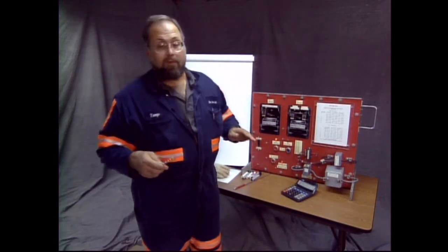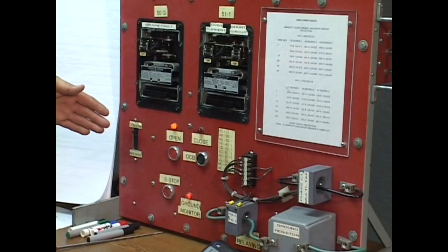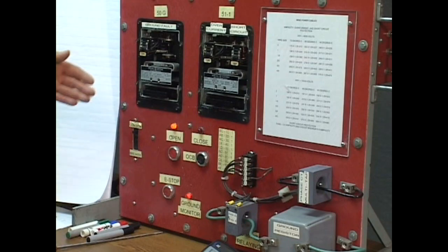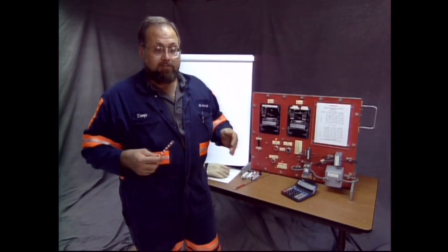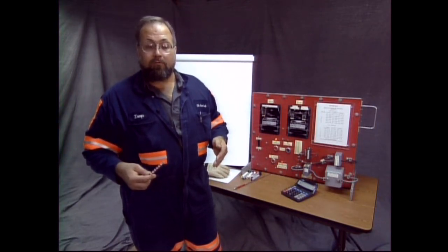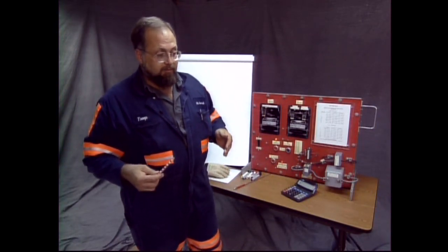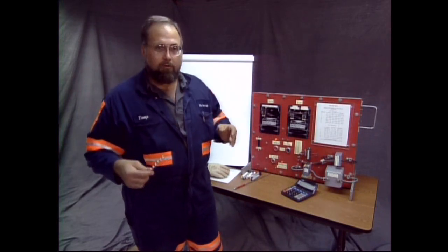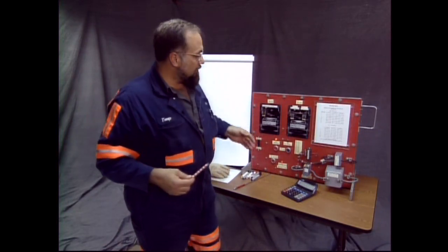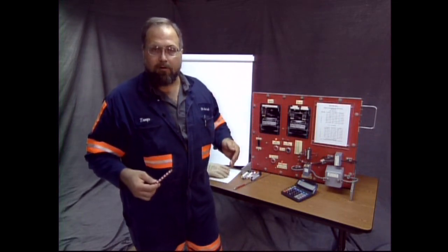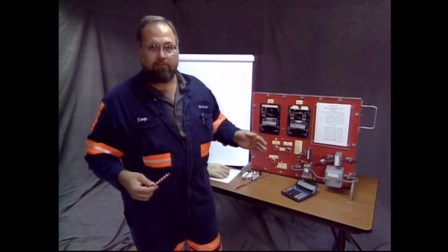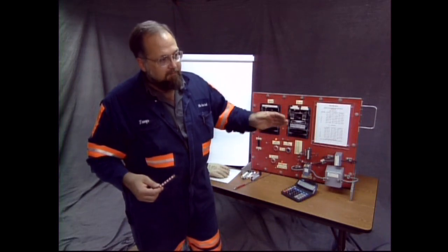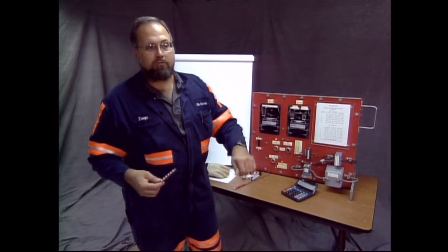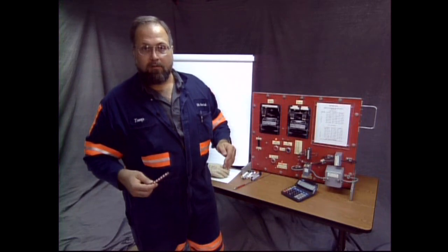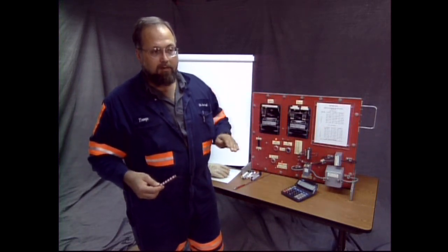So it has to be a visible, power removed. You're going to break the circuit with the oil circuit breaker or the vacuum breaker. It is designed to extinguish an arc if there is an arc. You know, you have all of your capabilities of breaking the circuit in the vacuum breaker. After you take the power off with the vacuum breaker or the oil circuit breaker, then open a visible. Look at the visible. Don't just operate the lever and walk. Look at it. Make sure you see 3 contacts separate all 3 phases.